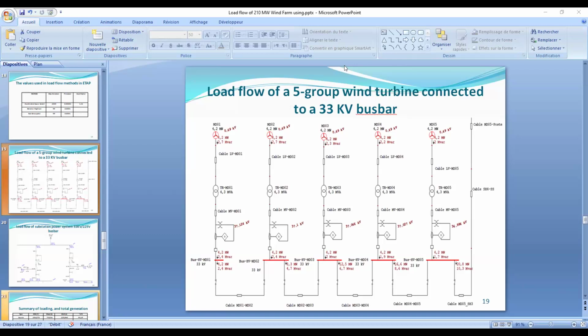And the figure shows the amount of overvoltage of the 33 kilovolts bus and the 0.69 kilovolts bus and overvoltage of the wind transformer. This figure represents the percentage of overvoltage of the wind farm transformer bus bar 33 kilovolts and 0.69 kilovolts. The critical and marginal voltage drop and overvoltage standards set by the utility are 5% and 10% respectively and are not significantly violated.